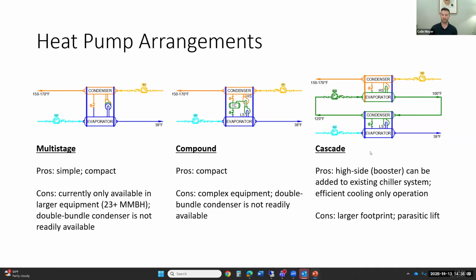And lastly, we have a Cascade, and this has been around for quite a while, although there are some newer products on the market with the latest refrigerants that can do the high side of a Cascade system. In a Cascade system, you basically got a conventional chiller on the low side, and you're heating water a little bit warmer than typical tower water, and then you're using that as a source to heat it further in another water-to-water heat pump. Downside of this is that you do have some parasitic lift because you're condensing on water tubes, and then you're pumping that around.